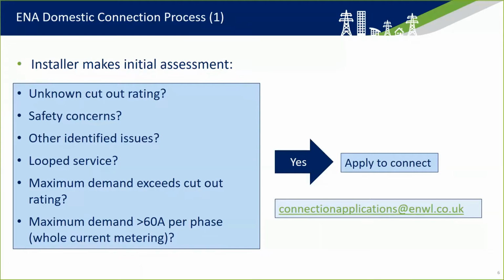Does the calculated maximum demand of the house and the EV or heat pump exceed the cutout rating? There are methods in the IET wiring regulations for calculating the domestic maximum demand. That's what we would recommend as a standard approach, and then add on the demand of the electric vehicle or heat pump on top of that. If the maximum demand is more than 60 amps, again, it would result in a requirement for applying to connect. So if the answer to any of those questions is yes, if you don't know the rating, if there are safety concerns, if there are any other issues identified, if it's looped, if the maximum demand is more than 60 amps, you have to apply to connect, and the email address for the application is given there.